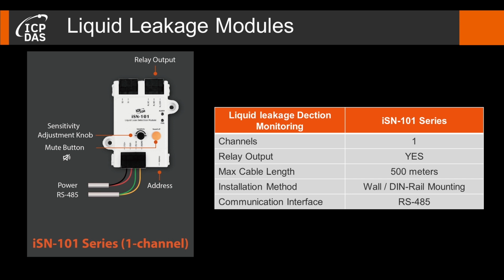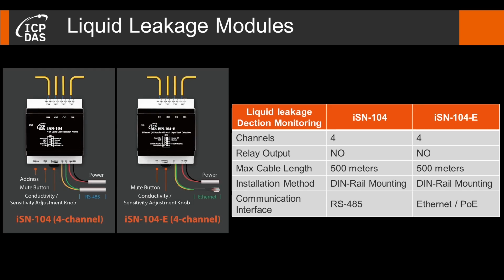ISN101 series module is a one-channel module and supports DCON and Modbus RTU protocols. In addition, it has an alarm function, which can send an alarm through the relay output to notify the on-site personnel. ISN104 IO module supports DCON and Modbus RTU protocols and has 4 channels which it can connect with 4 liquid leakage detection sensors. Each sensor can be placed at a different area to do the liquid leakage monitoring. ISN104-E has the same function as ISN104. The difference between the two modules is the protocol. ISN104-E supports Modbus TCP protocol.